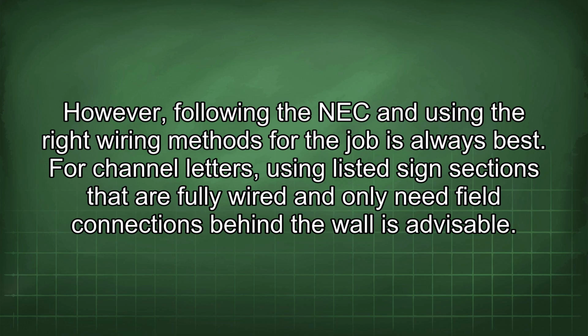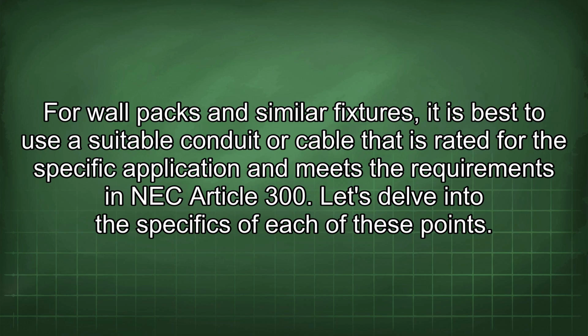For channel letters, using listed sign sections that are fully wired and only need field connections behind the wall is advisable. For wall packs and similar fixtures, it is best to use a suitable conduit or cable that is rated for the specific application and meets the requirements in NEC Article 300. Let's delve into the specifics of each of these points.